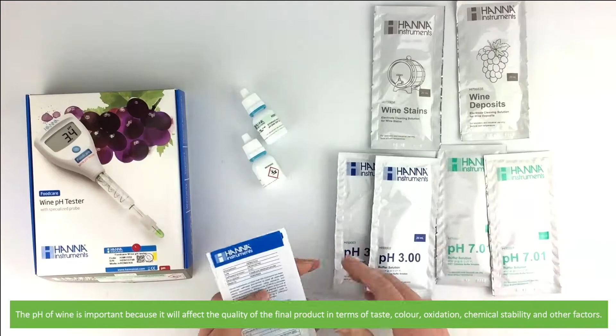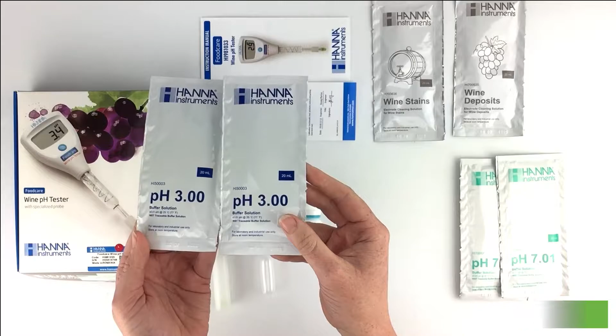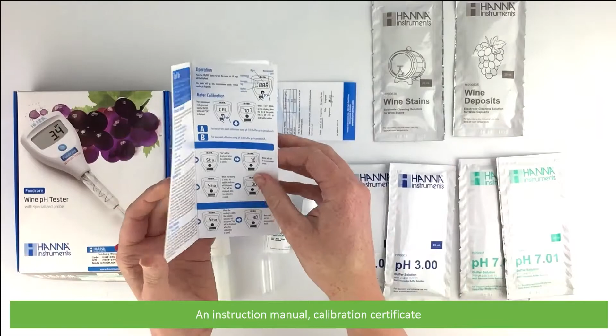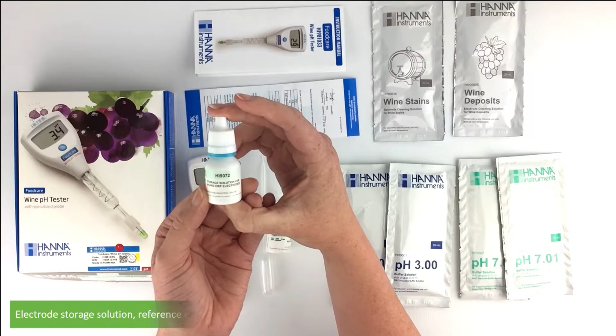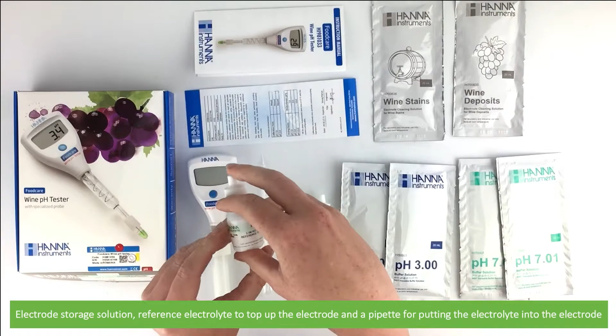In the box is some cleaning solution for wine stains and wine deposits, two packets of pH 7 buffer, 2 packets of pH 3 buffer, an instruction manual, calibration certificate, electrode storage solution, reference electrolyte to top up the electrode, and a pipette for putting the electrolyte into the electrode. And lastly, the wine pH tester.